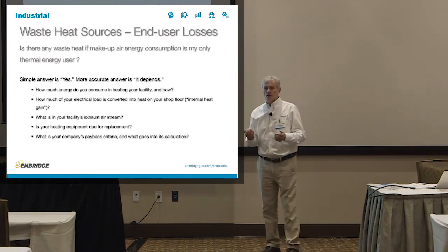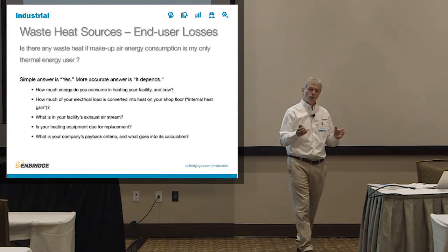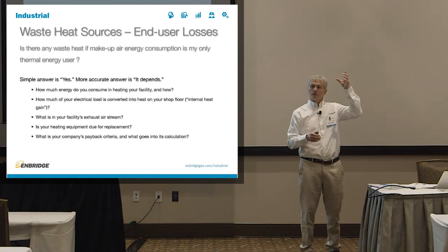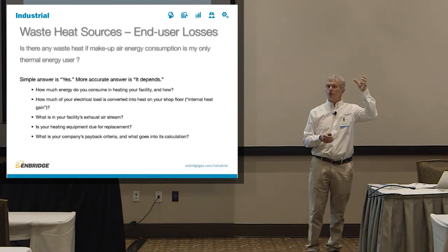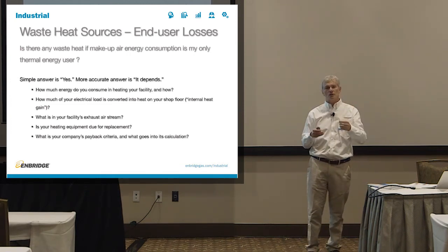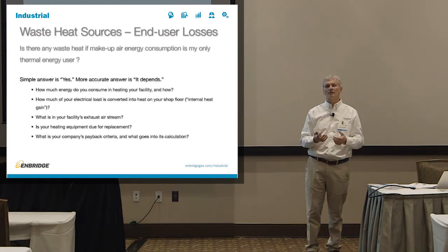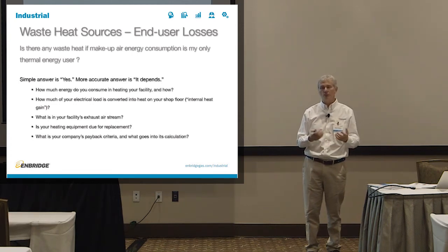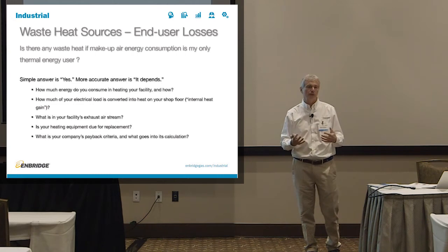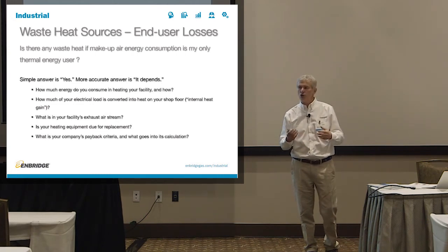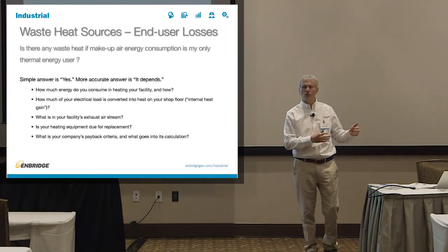What's your in-facility exhaust airstream? Again, if all you do is exhausting the space portion of your facility, not any process exhaust, just a space exhaust, typically you won't have anything bad in it. But if you do a lot of welding, you might have some particles in your exhaust. You have to be cognizant of it and know how to size your air exchange to suit.